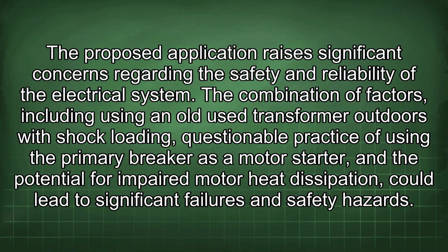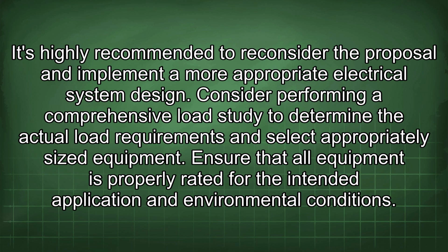The proposed application raises significant concerns regarding the safety and reliability of the electrical system. The combination of factors, including using an old, used transformer outdoors with shock loading, the questionable practice of using the primary breaker as a motor starter, and the potential for impaired motor heat dissipation, could lead to significant failures and safety hazards. It's highly recommended to reconsider the proposal and implement a more appropriate electrical system design.